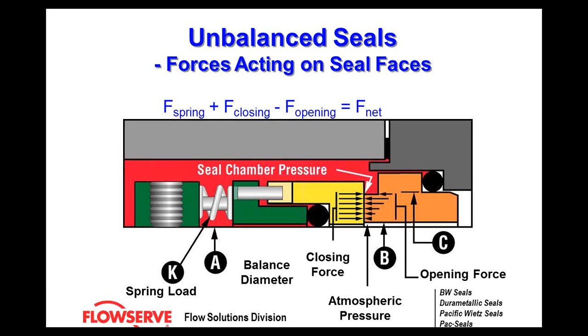For an unbalanced seal, the equation is: closing force of the springs plus closing force of all other factors minus the opening force equals the net force. Looking at the seal itself, where the springs are located at item K — if you draw a line straight through that spring, you'll notice the springs are directly in line with the interaction of the two seal faces. That is indicative of an unbalanced design.